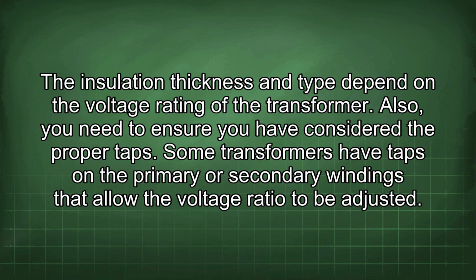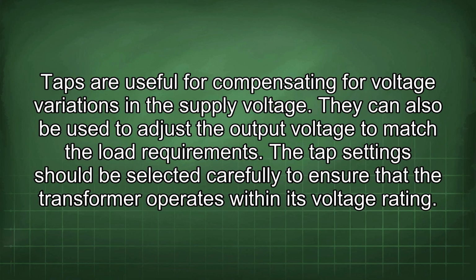Also, you need to ensure you have considered the proper taps. Some transformers have taps on the primary or secondary windings that allow the voltage ratio to be adjusted. Taps are useful for compensating for voltage variations in the supply voltage. They can also be used to adjust the output voltage to match the load requirement. The tap settings should be selected carefully to ensure that the transformer operates within its voltage rating.